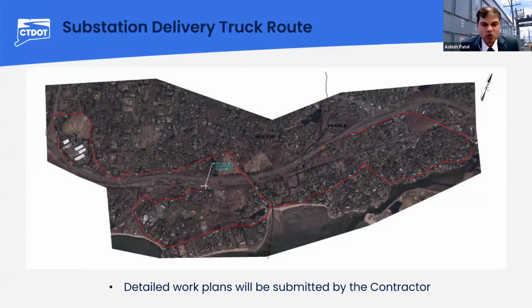This slide shows the substation enclosure and auto transformer delivery truck route starting from I-95 North or I-95 South, depending on the trucking company's choice, to the proposed site location. The contractor will be using the crane to unload the substation enclosure from the delivery truck to the substation vault foundation, as well as the auto transformer from the delivery truck to the auto transformer foundation. Substation delivery, auto transformer delivery, and unloading process may take approximately 4 hours from start to finish. The main goal is to deliver the balancing substation at the project site without any kind of impact or incident. The proposed work plan will be submitted way prior to the delivery date being scheduled.